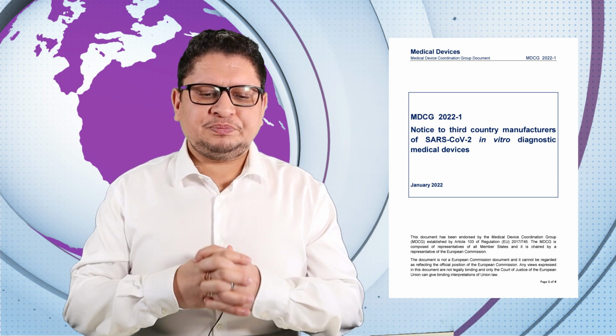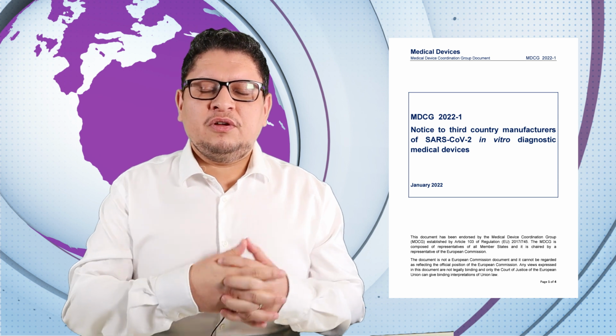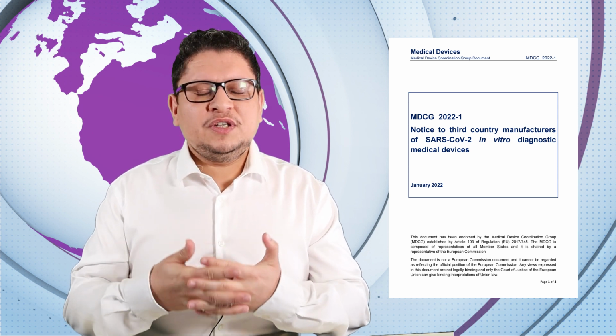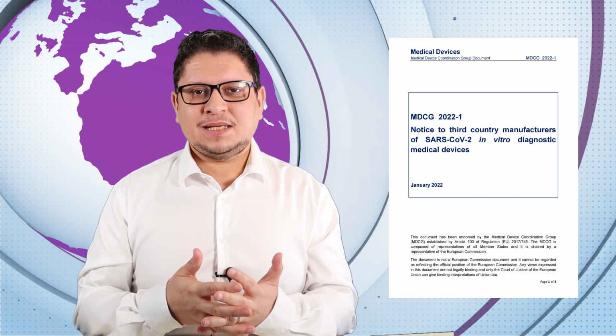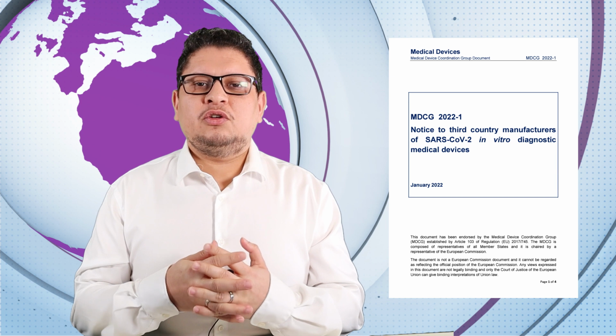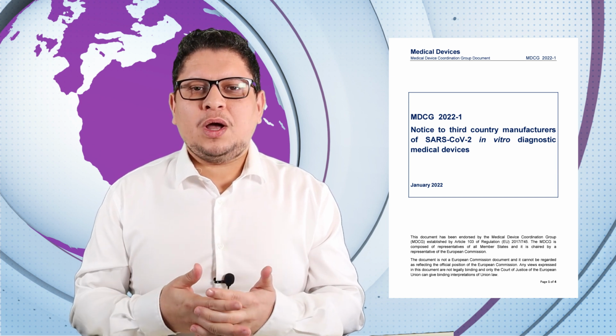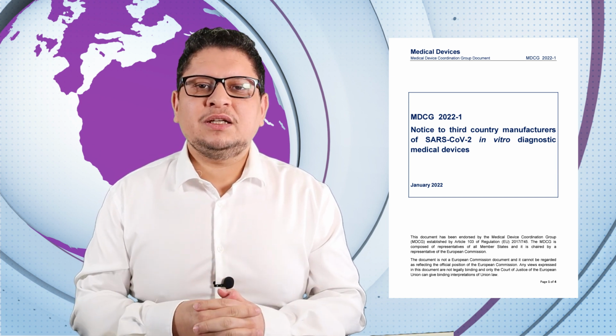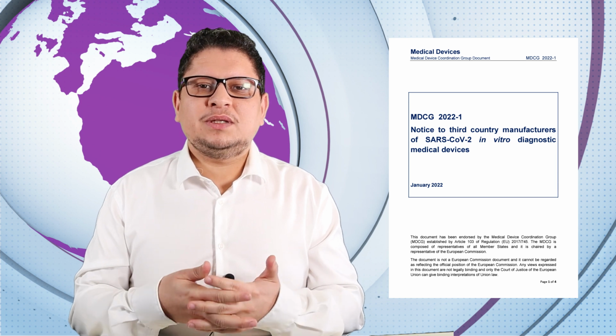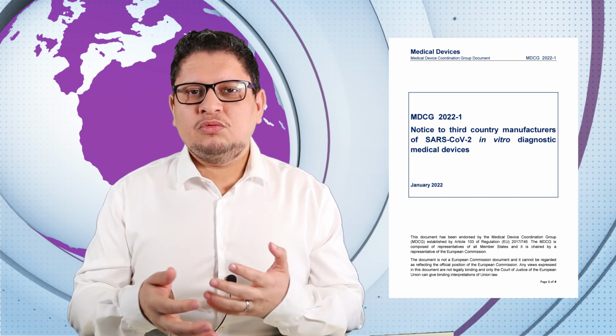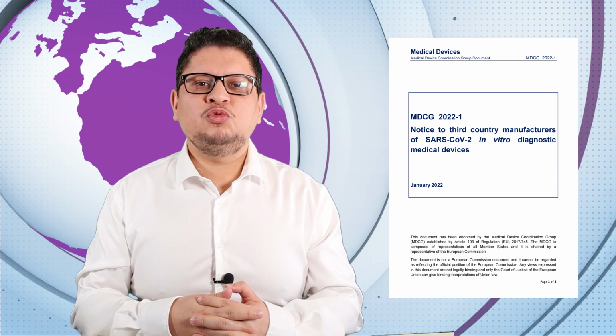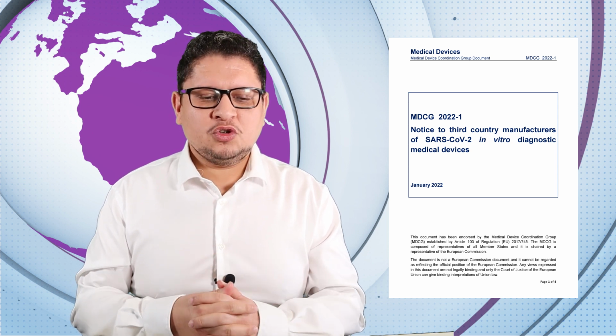Then, as we talked about with the Finnish organization, there are a lot of issues with the fact that many self-tests are not certified by a notified body. As I've told you, the rule is that when we have a self-test for SARS-CoV-2, you have to have a notified body certifying the product. Without that, we cannot guarantee that a layperson is really well qualified to do the self-test by themselves. So this is the second one.